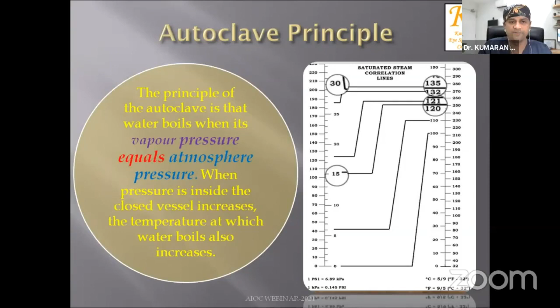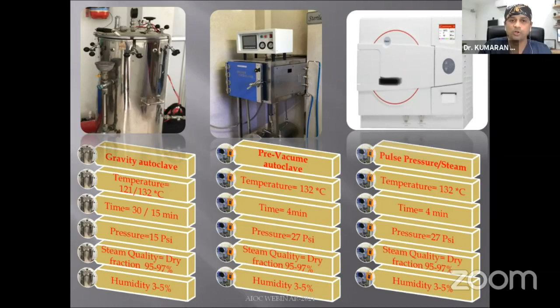There are 3 different types of autoclaves which we use in a clinical practice, and based upon the type of load which you are going to process, you have to use a gravity autoclave, which is useful in non-porous and non-hollow instruments. The pre-vacuum and the pulse vacuum basically remove the air inside the autoclave to make the steam process more effective. Then whatever autoclaving you've done, quality assurance of sterilization is very important.